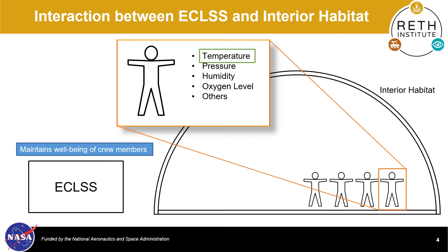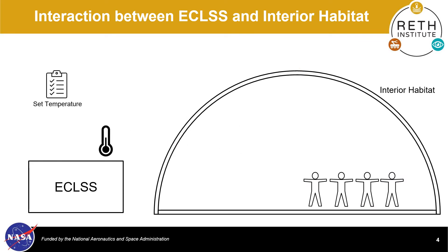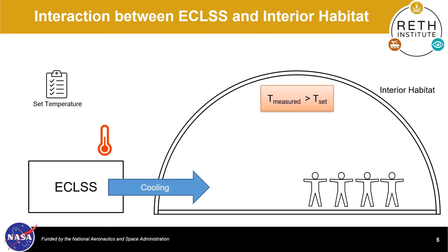Interaction between ECLSS and the Interior Habitat System takes place in a very simple manner. ECLSS receives temperature measurement information from the Interior Habitat System and compares that to the set point temperature. Assuming that it has a sufficient power supply, ECLSS will provide cooling to the habitat if the measured temperature is higher than the set point temperature, and will provide heating if the measured temperature is lower than the set point temperature.